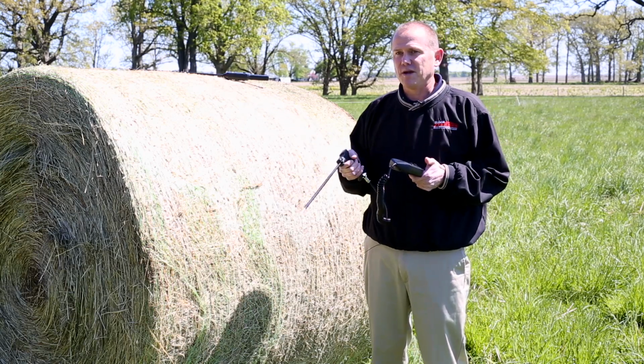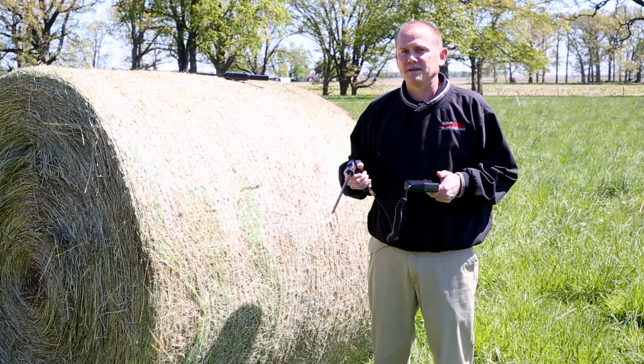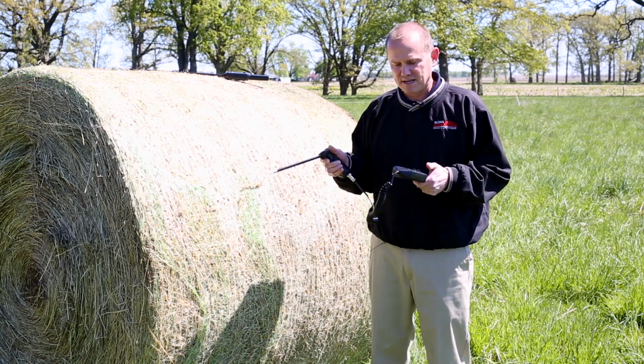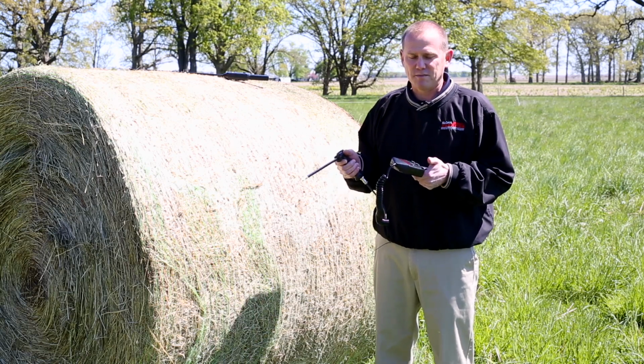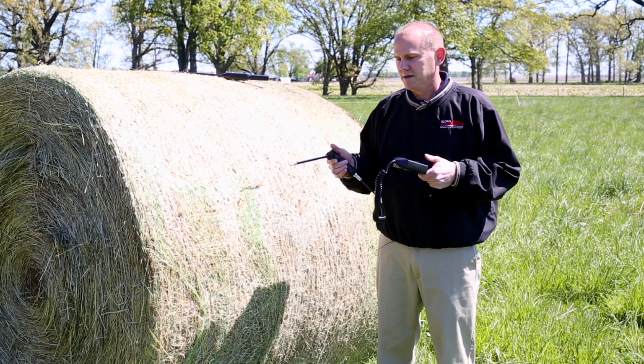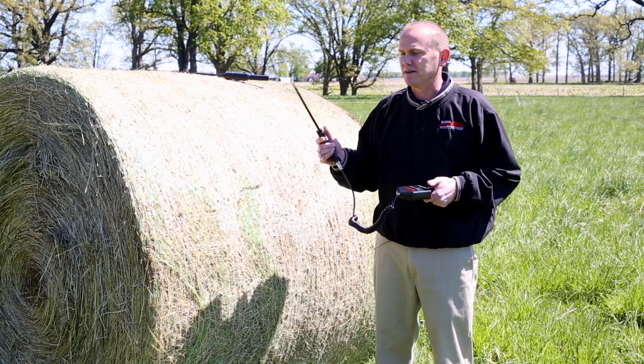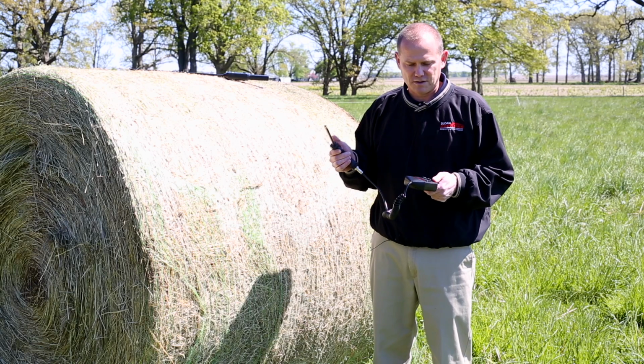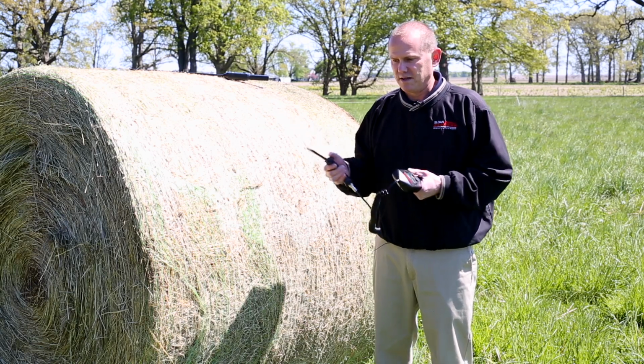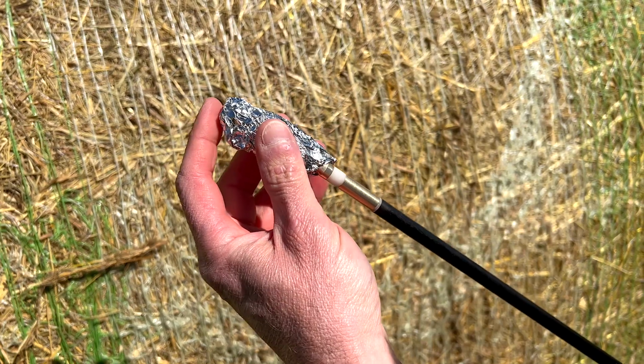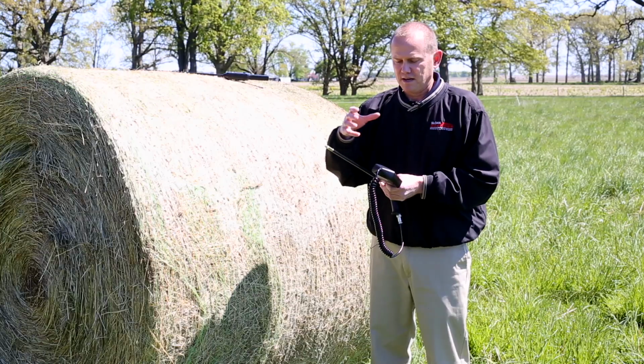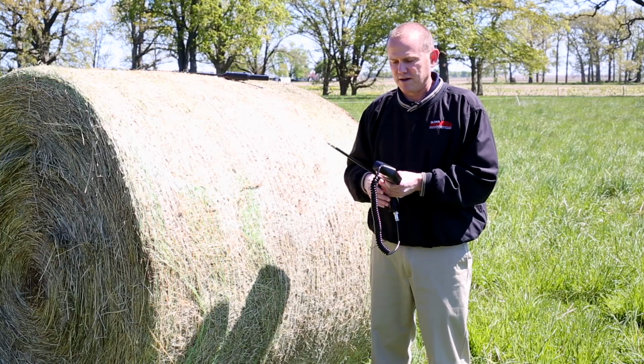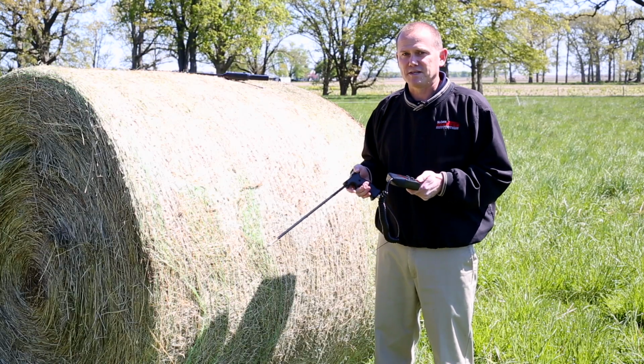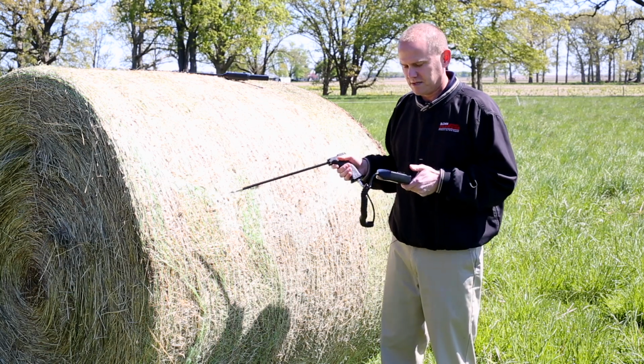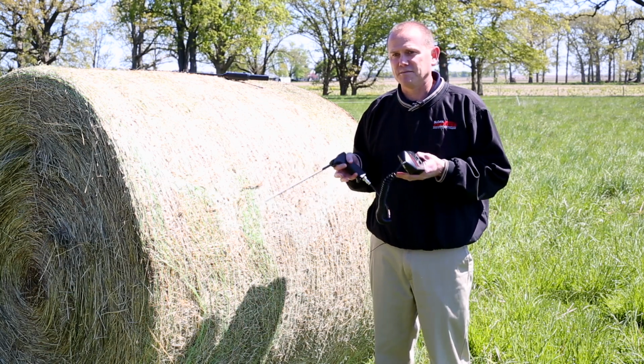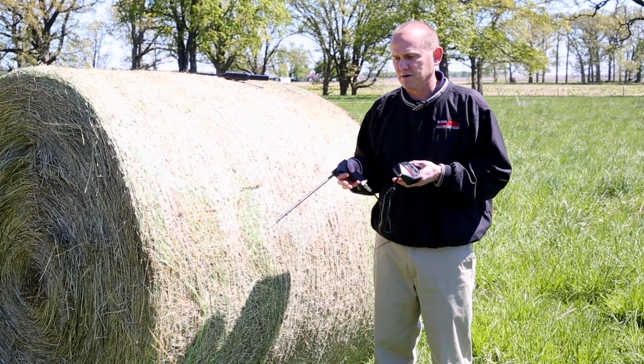It will be a range from 14.5% up to 45, and that's easy to tell because when you first power it up, it'll take a little bit of time when you first start it, but once it gets first readout in open air, it'll be 14.5. So you know it's already set up and ready to go. And then if you covered it with like aluminum foil, it should go to 45, and that'll tell you it's actually calibrated and ready to go. It will take a little bit of time when you first test your hay, so you want to give it a little bit of time in the bale to get a good readout.